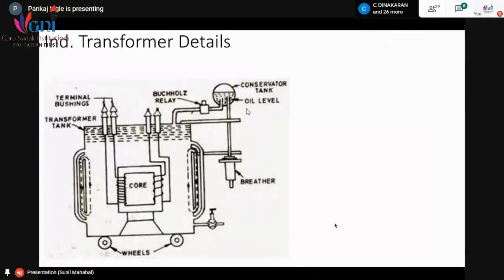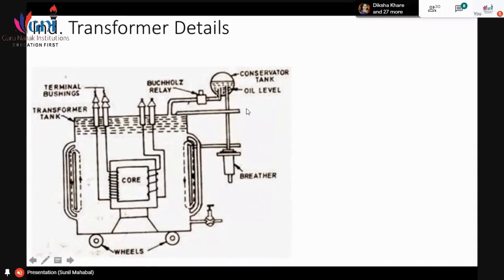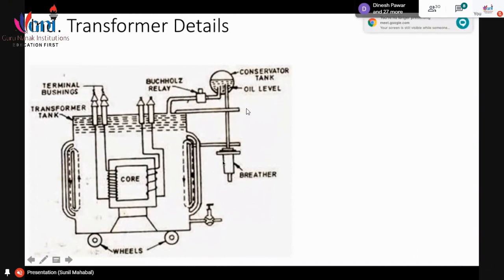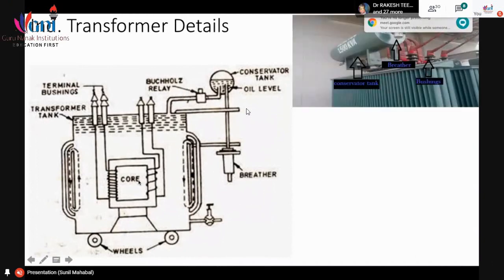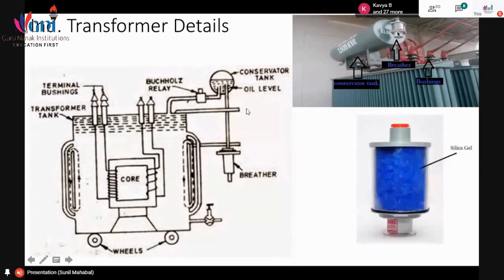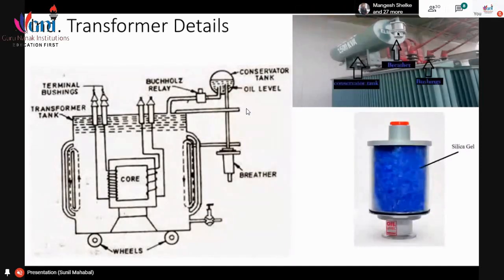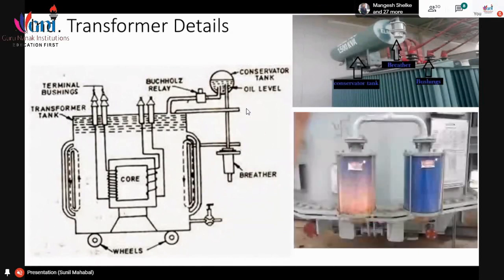Okay. Then the main transformer, industrial transformer details. So these are the 11 kV by 440 transformers, delta star. And here you can see in the picture the conservator tank, oil level, Buchholz relay, and the breather. This is the breather from where the air enters, and to trap the moisture in the air, this breather has silica gel or CuSO4. So this is how it looks when it is fresh. But once it absorbs the moisture, it changes its color, and then you have to replace it with a new one.